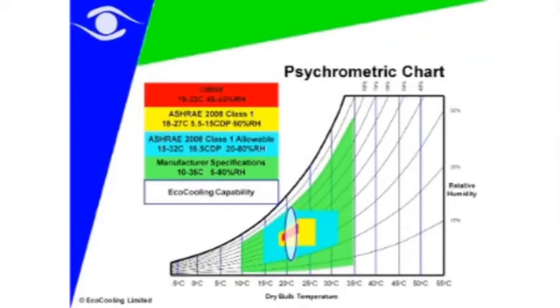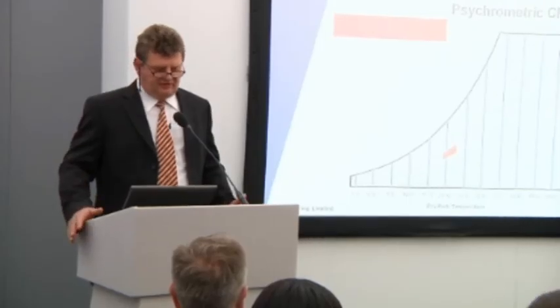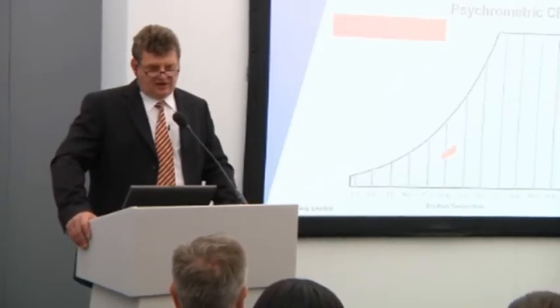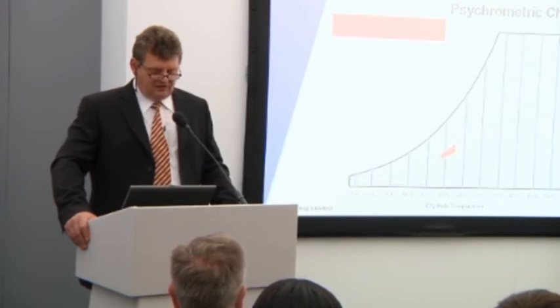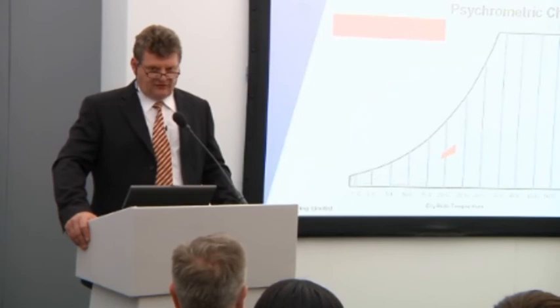Let's look at this on the psychrometric chart — the tool that engineers use to understand the relationship between air and water. There is temperature across the horizontal axis and specific humidity vertically. The hotter air gets, the more water it can support. Most data centres and server rooms have been designed to the typical UK guidelines from CIBSE — the Chartered Institute of Building Service Engineers — which specify 19 to 23 degrees centigrade and 45 to 55% relative humidity.